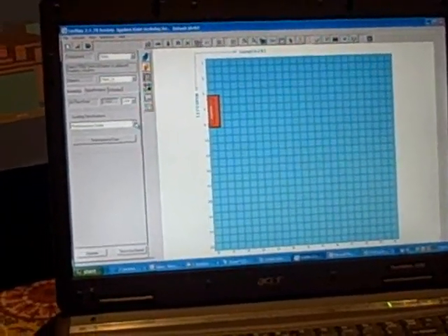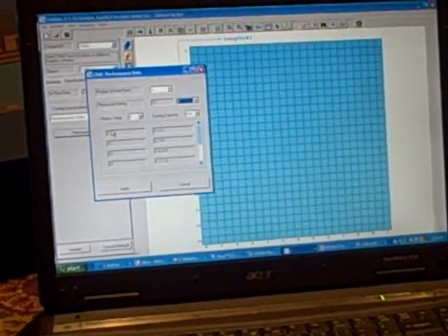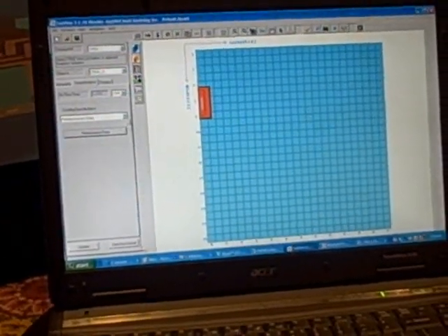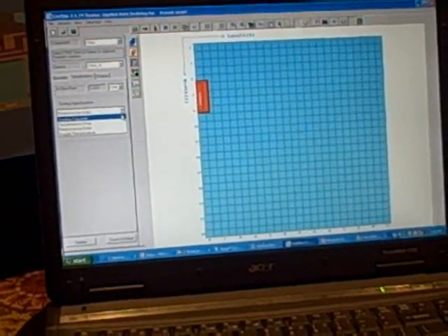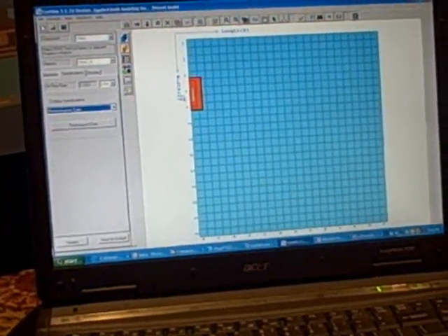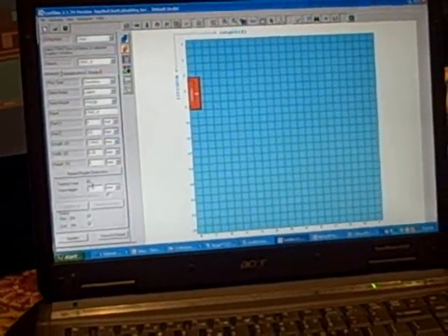Now in terms of specifications we're able to model that CRAC as standard performance data which allows you to take a look at the performance of the CRAC as a function of return temperature. Or you can model it as cooling capacity, constant cooling capacity, or temperature drop, or constant supply temperature. We'll choose performance data for this one. We can also model this with turning vanes on, and we can also set the height of the turning vanes to be whatever we like.